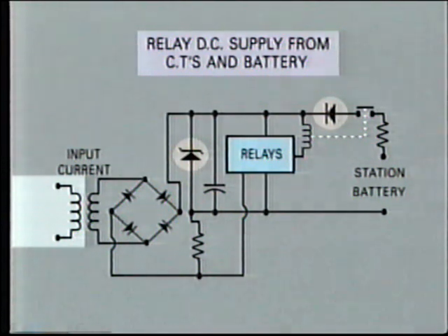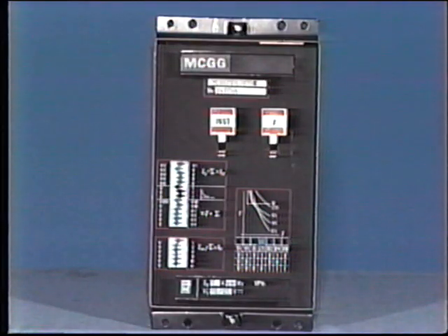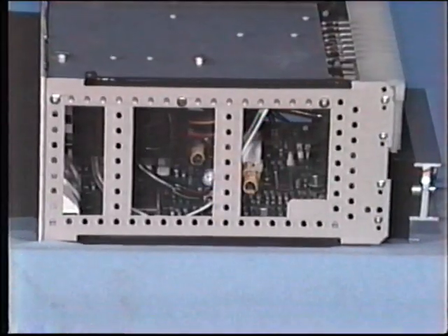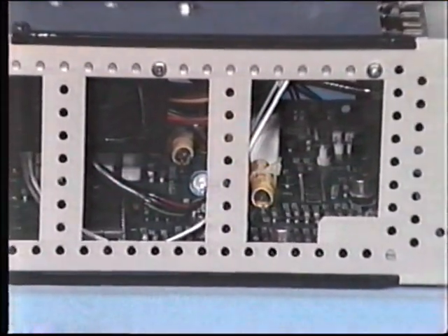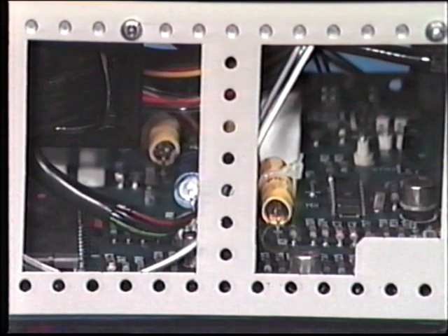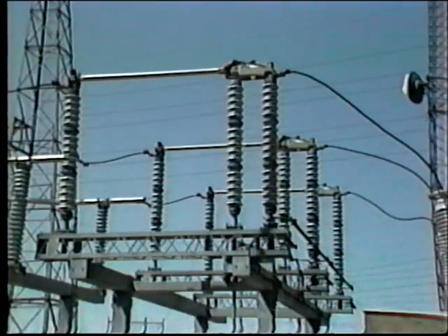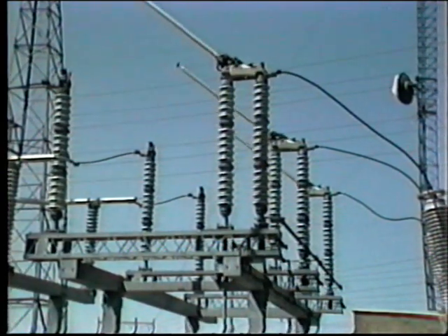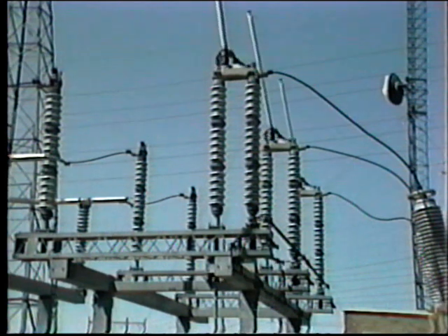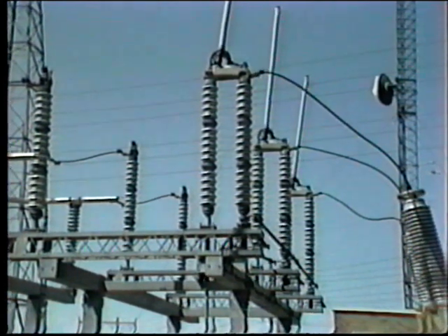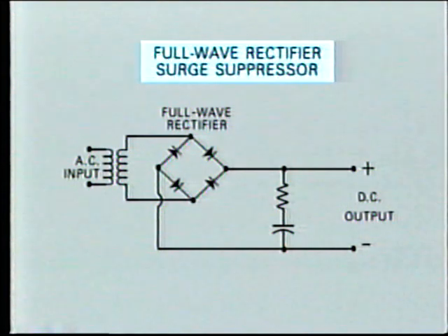Where the power source is AC, it is extremely important to protect the static relay against transient overvoltages or voltage spikes. These spikes may damage semiconductor components and at the very least will cause incorrect operation. Voltage spikes can be caused by normal operations on the power system, such as switching or system faults. Protection for the relay is provided by connecting surge diverters at appropriate locations.